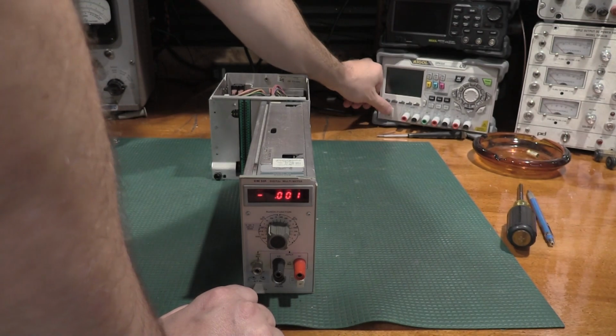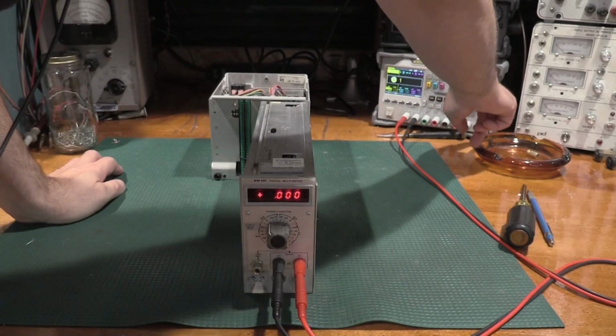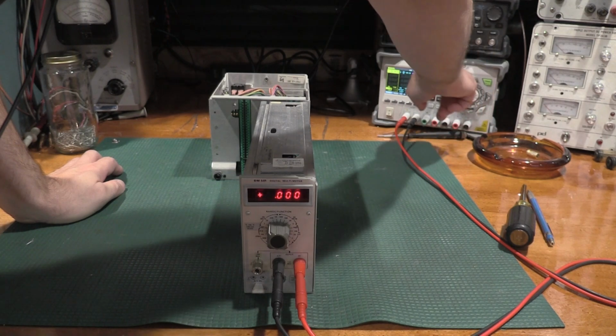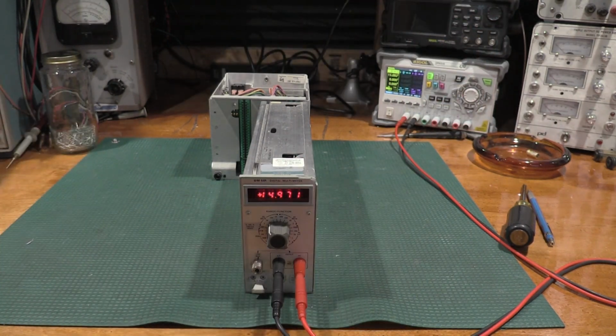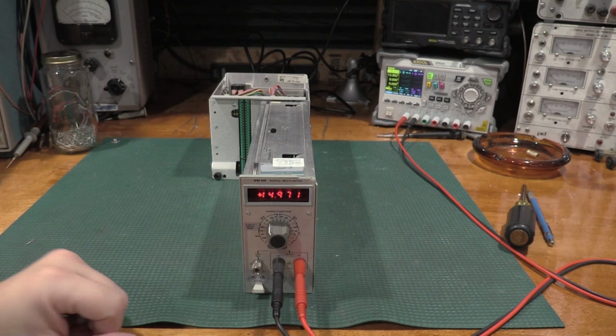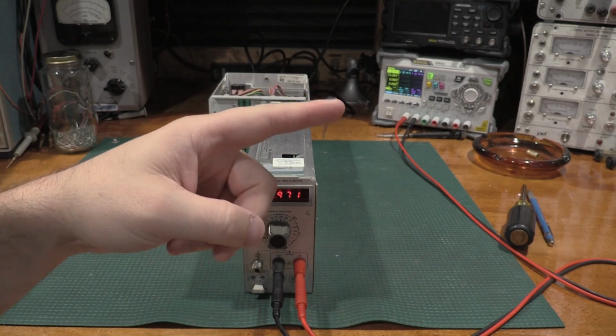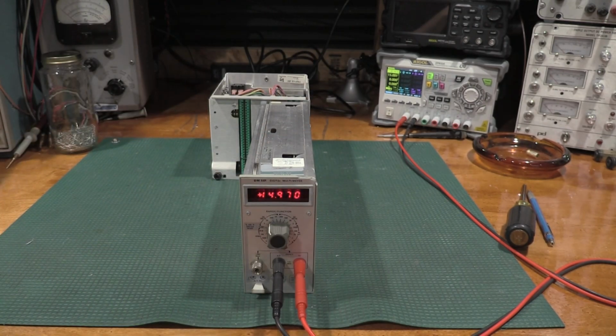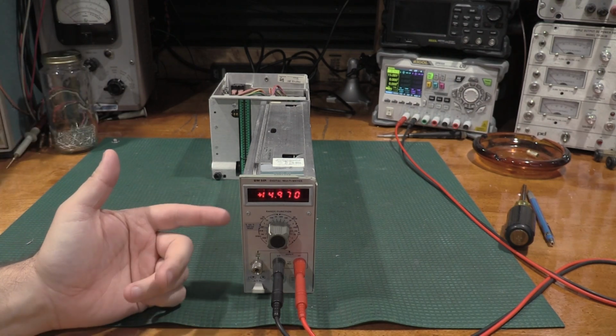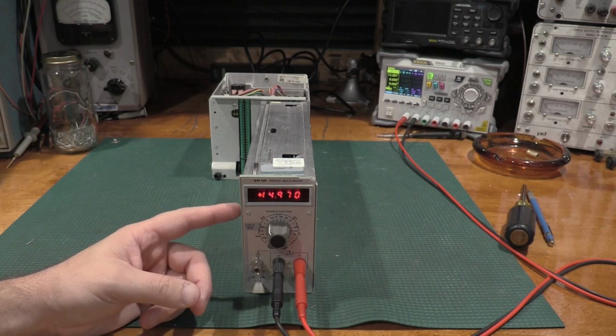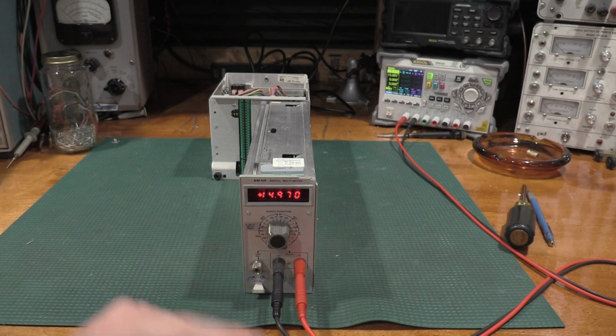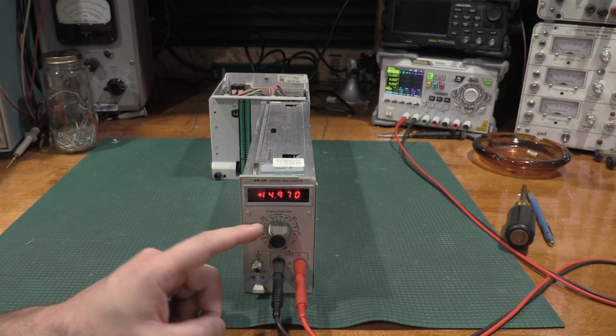Let's just throw on a power supply. We'll set it for 15 volts DC, 3 amps. It's not going to move much at all. 14,971. Not bad. Is very possible. I do know the Rigol is usually off by about 3 millivolts, so not too crazy. We'll really want to check this versus the DC standard after it finishes warming up.